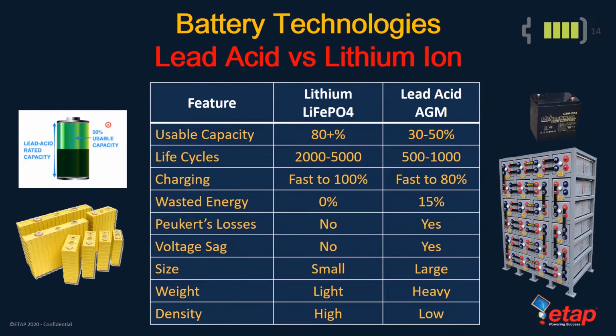The faster you discharge a lead acid battery of any type, the less energy you can get out of it. This is also known as Peukert's loss, and there is essentially Peukert's law named after the German scientist W. Peukert, which says that in practice, high current loads like air conditioners, microwaves, induction cooktops, can result in a lead acid battery being able to actually deliver as little as 60% of its normal capacity. This is a huge loss in capacity when you need it the most. Related to the loss is also the voltage sag that is experienced when the battery is applied to a large current load. And finally, on the dimensions, we can see the size, weight, and the current density of the lead acid battery is large, heavier, and lower current density as compared to a lithium-ion battery of similar capacity.